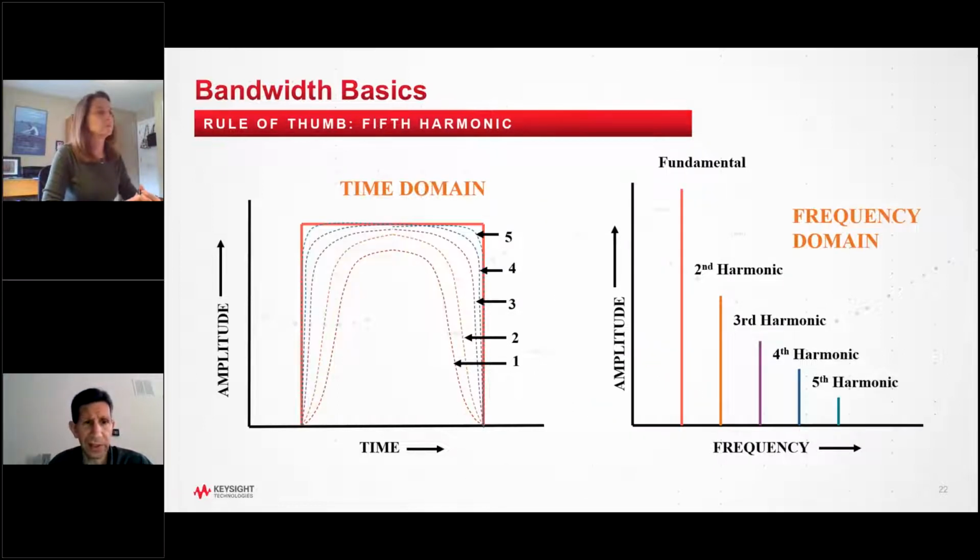Again, you've seen that slide that we had before. The general rule of thumb is 5th harmonic, without consideration for other advanced techniques like signal interpolation.